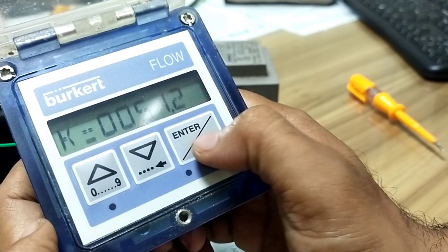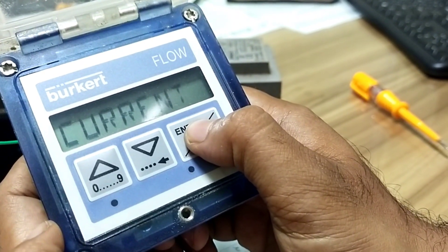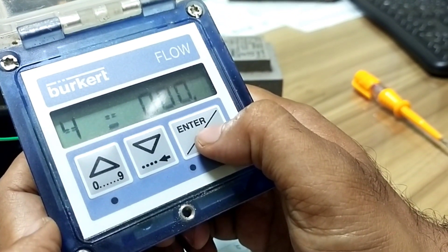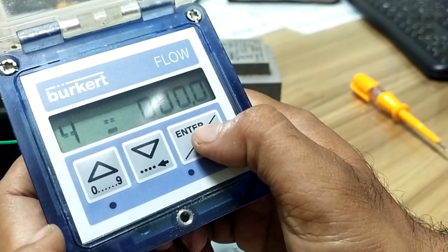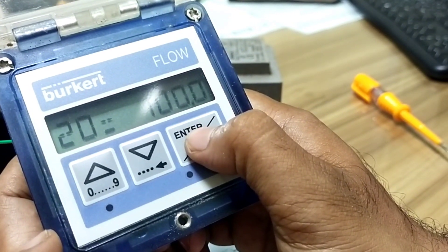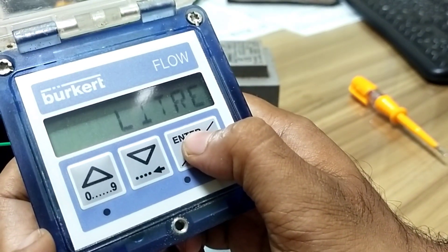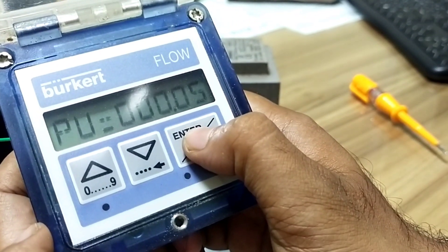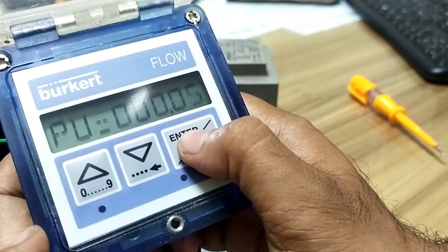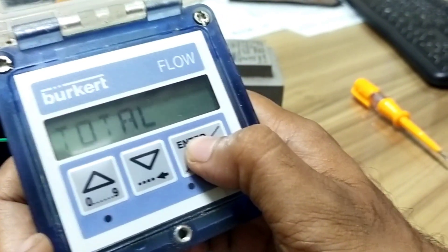K factor is set to 51.20. Built-in data: current at 4 milliampere is zero liters, and at 20 milliampere is 100 liters. Setup is finished. Pulse set to 0.005 per pulse per liter. Filter set to 5. Total reset: no.